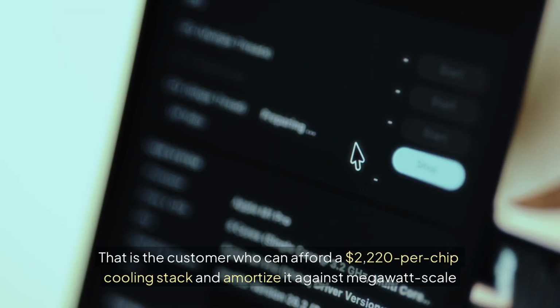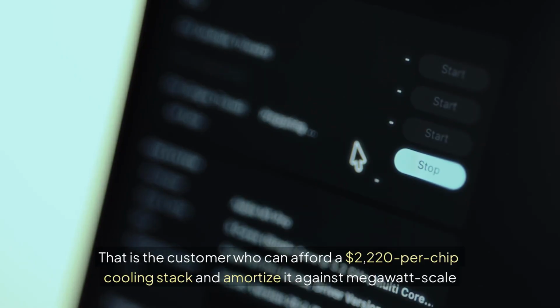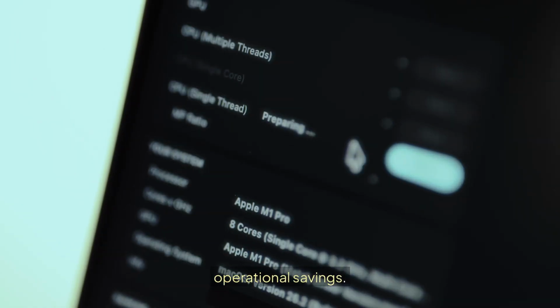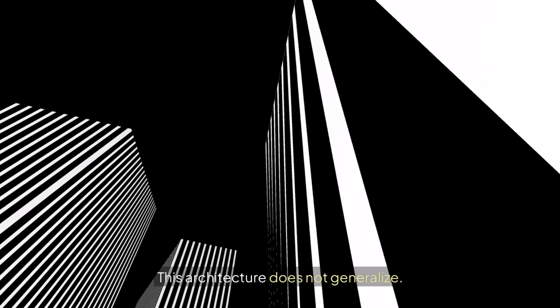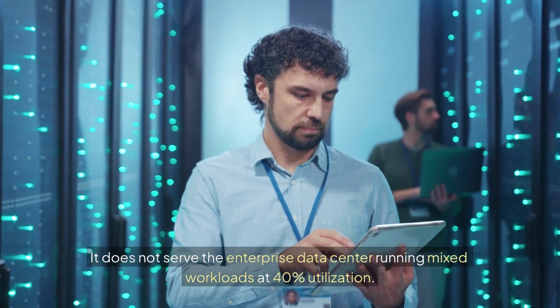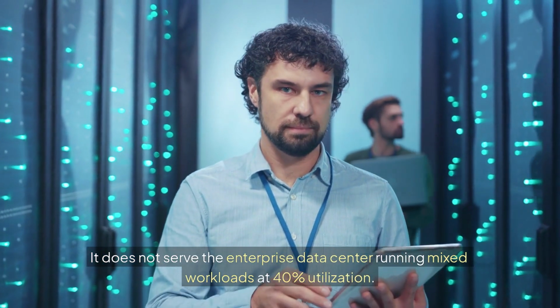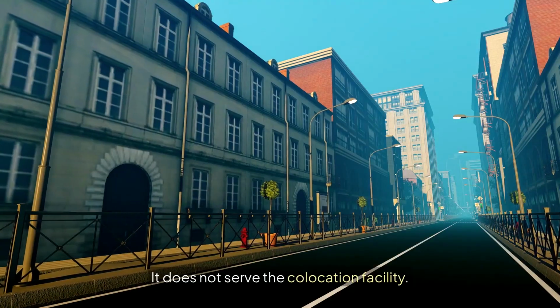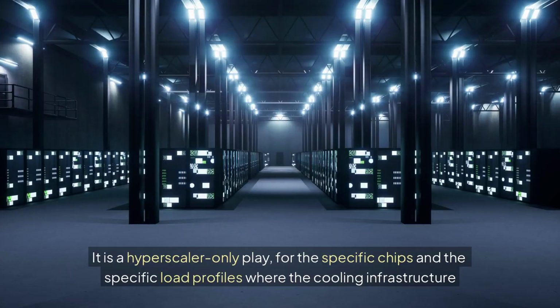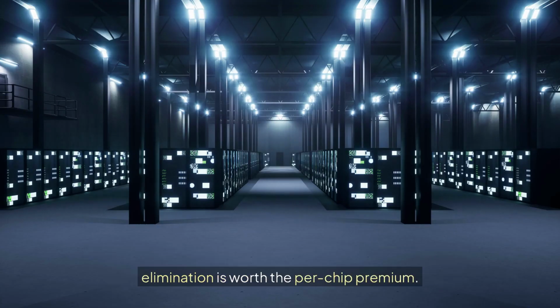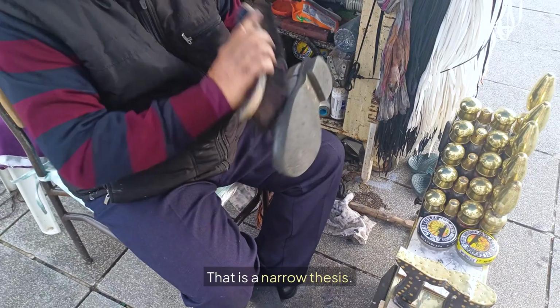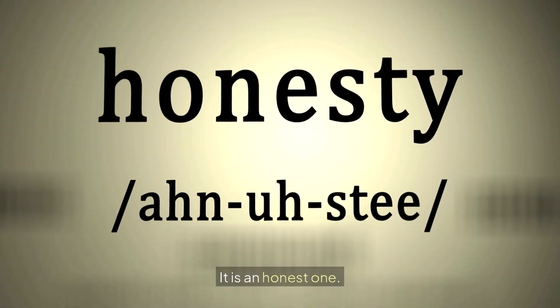That is the customer who can afford a $2,220 per chip cooling stack and amortize it against megawatt-scale operational savings. This architecture does not generalize. It does not serve the enterprise data center running mixed workloads at 40% utilization. It does not serve the colocation facility. It does not serve the edge. It is a hyperscaler-only play for the specific chips and the specific load profiles where the cooling infrastructure elimination is worth the per-chip premium. That is a narrow thesis. It is an honest one.